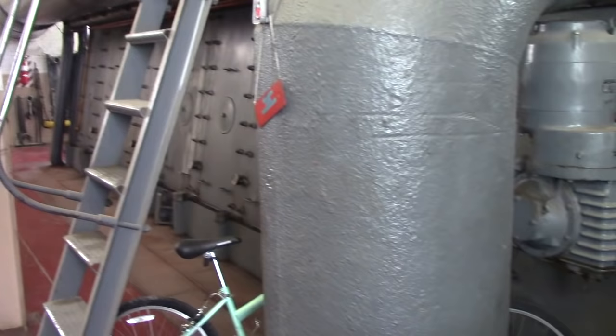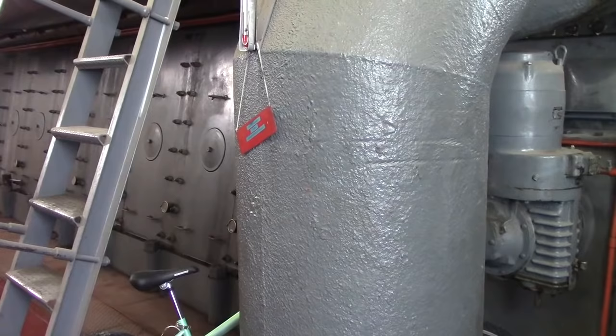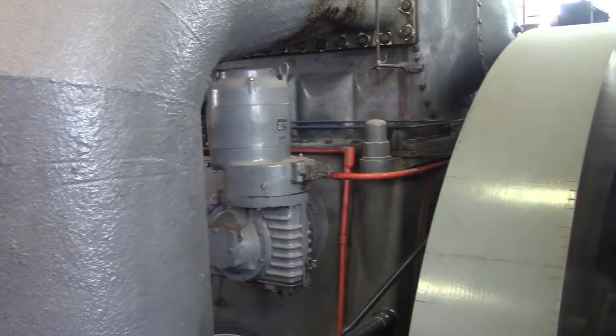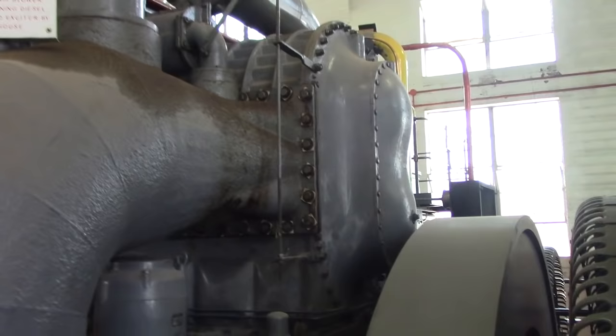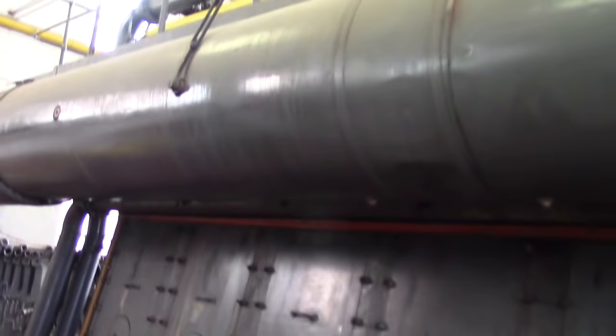You can see each cylinder here, how it's attached to the crankcase, all bolted down. Here's the generator right next to the Fairbanks Morse, and it has a nice little sign. This is a Nordberg engine, installed 1951, 3440 horsepower, 2160 kilowatts, two-cycle engine. This one is set up for both diesel fuel and natural gas. It has a blower — the blower is about four feet tall. Down here on the crankcase are the explosion release doors, in case you have a crankcase explosion. This big pipe right here is the exhaust manifold.